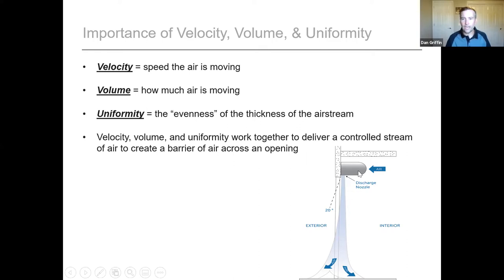In this diagram, you can see the air curtain installed on the inside of the building. You want it installed as close to the top of the door as possible. There's an adjustable panel on the back of the air curtain — you can adjust it 20 degrees in or out. Typically you adjust it toward the outside of the building at about a 20-degree angle, which gets your split right outside the threshold of the door for the best protection.